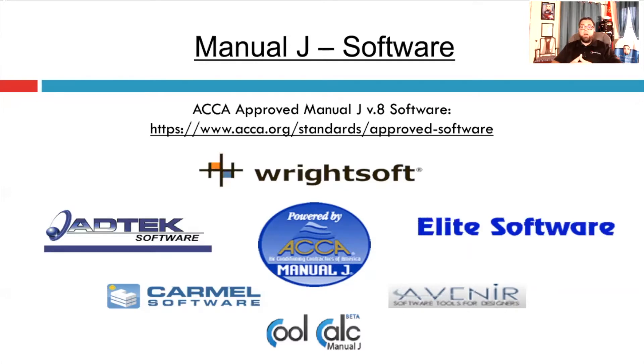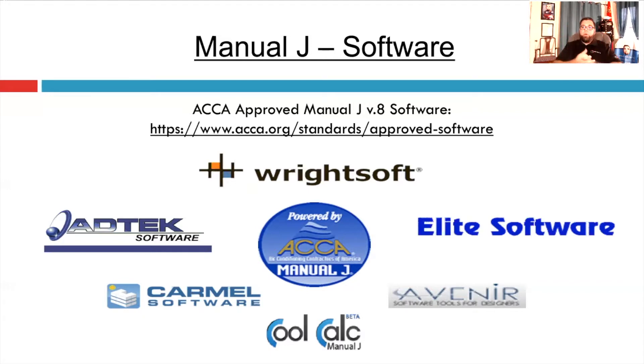There is Adtek or elite software, which is more of a worksheet style for data entry as opposed to drawing out the floor plan. It's a little tougher on verification, and a lot of local building inspectors have a tougher time with those style reports — they really love Wrightsoft because it's easy to verify. Carmel is an Apple iOS software used on an iPad. Like Adtek and elite, it's checklist-based: you enter each wall, what's on it, the insulation value, the direction it faces. It's tougher to do a room-by-room load calc on Carmel — you'd do a block load first and deduct walls for each room.